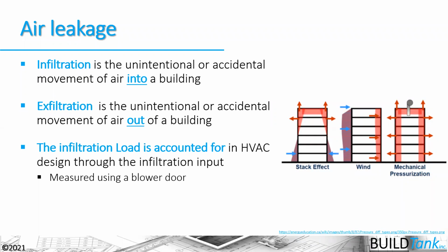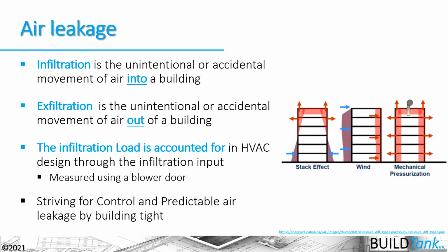The infiltration is accounted for in the HVAC design, and we can measure the infiltration and make it more precise in its accountability in the HVAC design if we use a blower door. So we'll learn a little bit later on if there's an assumption that you can make on how airtight the house is, or you can use a more accurate measurement that comes through the blower door there. But ultimately, what we're striving for is to get this control and predictability of air leakage.